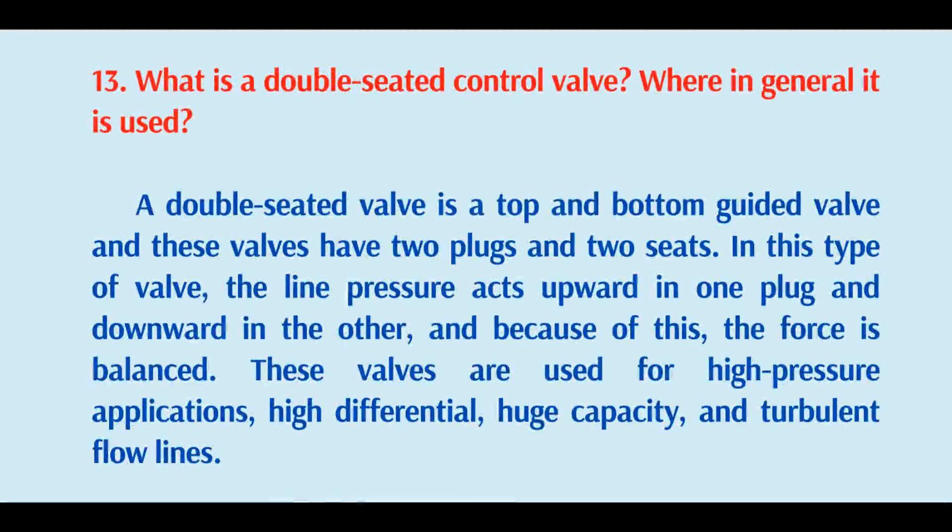What is a double seated control valve and where is it generally used? A double seated valve is a top and bottom guided valve. These valves have two plugs and two seats. The line pressure acts upward on one plug and downward on the other, balancing the force. These valves are used for high pressure applications, high differential, huge capacity, and turbulent flow lines.